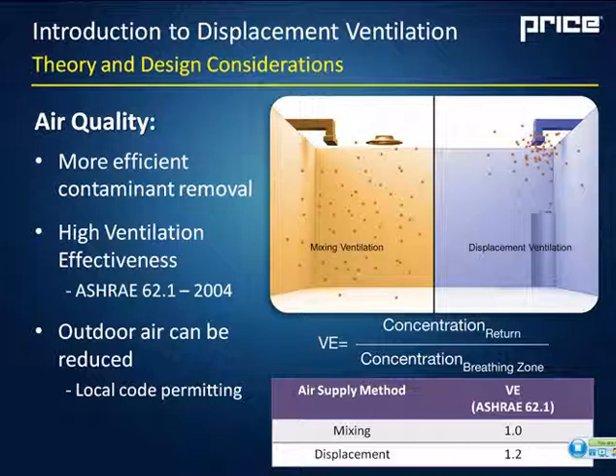And now if you're doing your outdoor air requirements per ASHRAE 62, you can actually get an outdoor air requirement discount, so that you take your outdoor air requirement based on the number of people in the room and the square footage, and you divide that by 1.2, so you're really saving around 17% on the outdoor air.